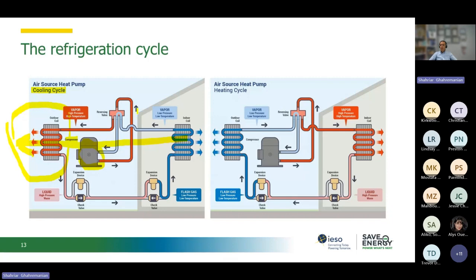What's really good, and different from a standard air conditioning system, is the reversing valve - some people call it a three-way valve. This reversing valve does the magic for us and can switch the system from cooling to heating. If we reverse it for the heating season, in winter, we move heat from outside and bring it indoors. The components all remain the same - the refrigerant, the outdoor unit, the indoor unit - only the task of the outdoor unit and the indoor coil changes.